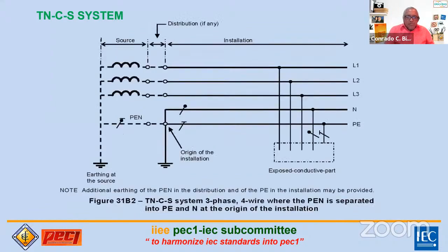Then we have the very common dito, immediately. Kung binigyan tayo ng, for example, utility, three-phase four-wire, then dun mismo sa origin ng installation, dito muna siya i-separate, yung dalawa, neutral and the PE. So this is how it's being connected. So additional earthing, hindi na pinoprohibit yan na magkaroon ka ng additional earthing of the PEN in the distribution kung maglalagay ka dito. So again, the exposed conductive part is connected to the protective earth conductor. So yan yung TNCS system.